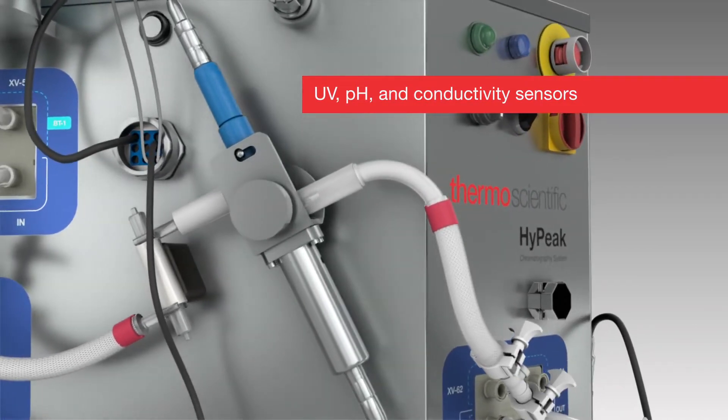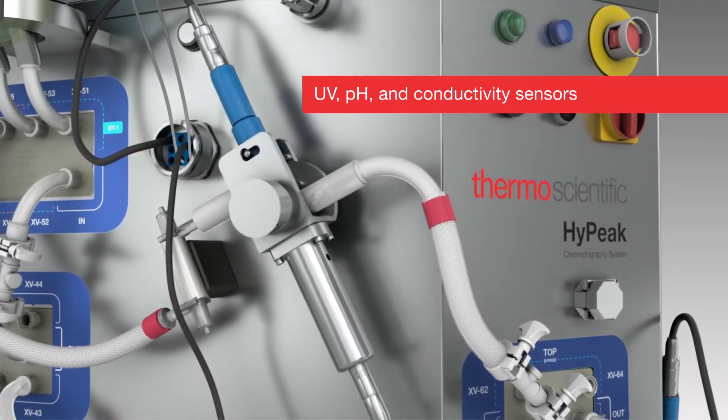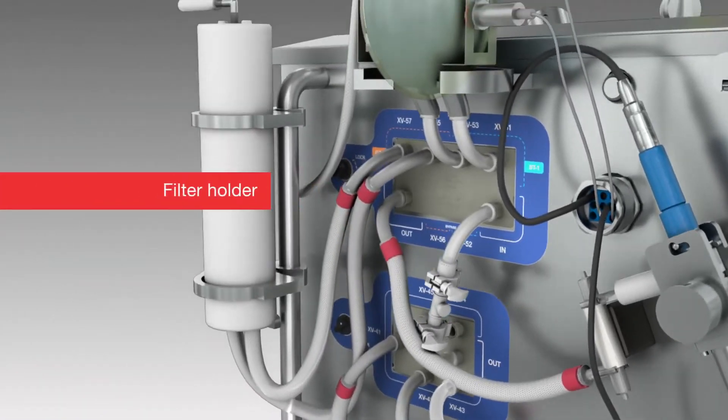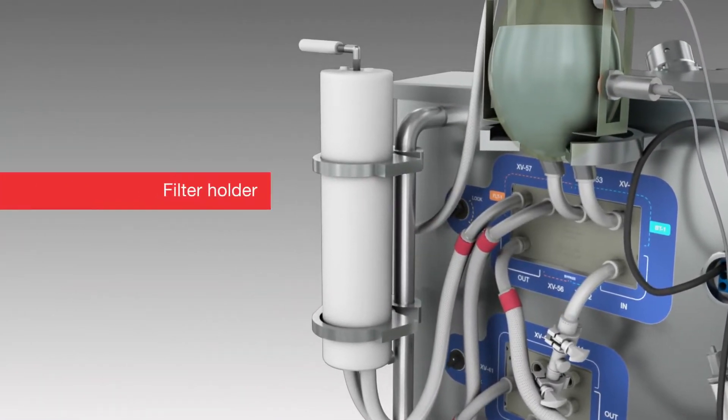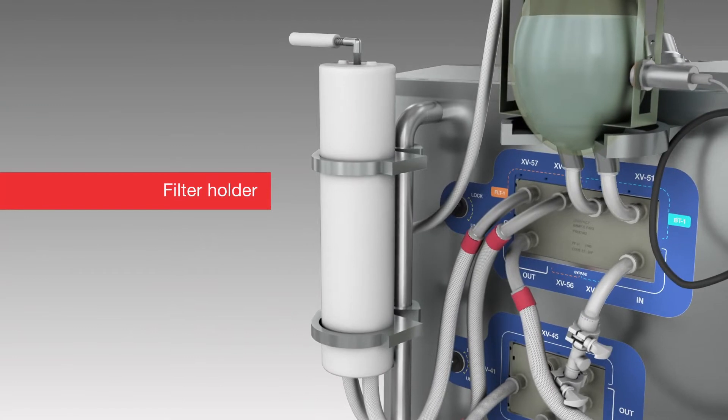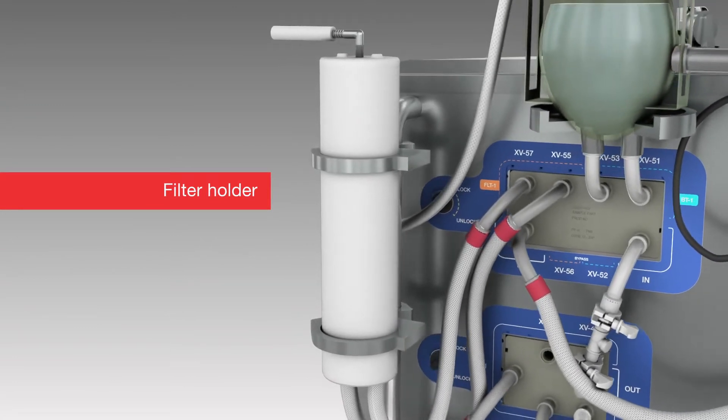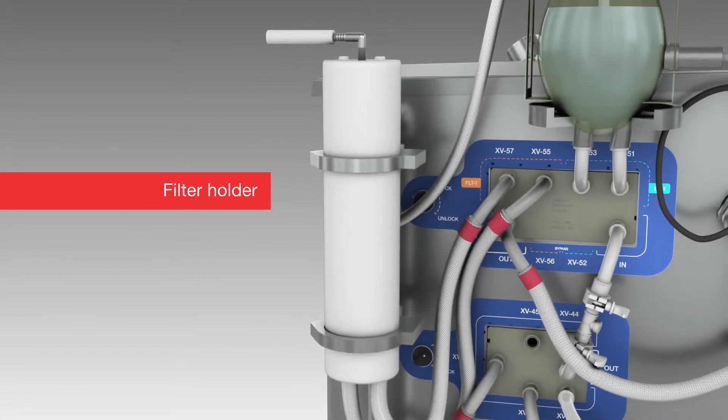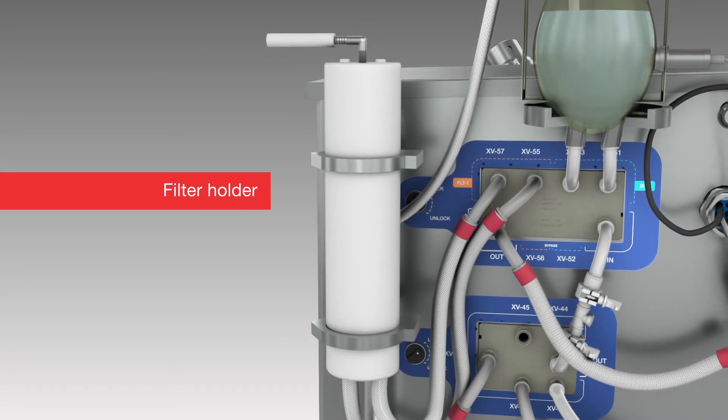UV detection is offered in multiple wavelength options to suit the process needs. A filter holder at the column inlet is provided as standard, and an optional contamination-free single-use filter assembly is available to install and use to avoid particle blockage of the column.